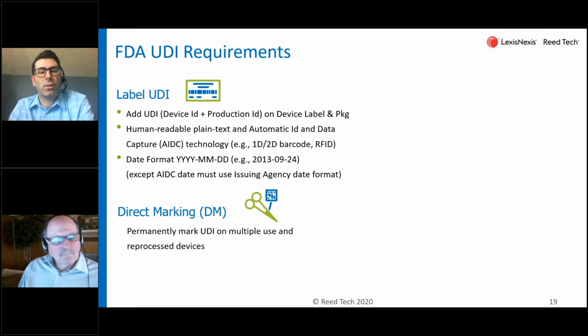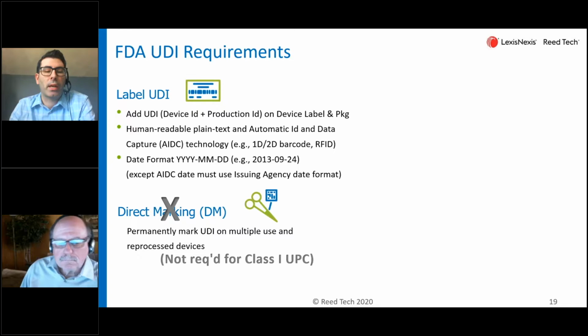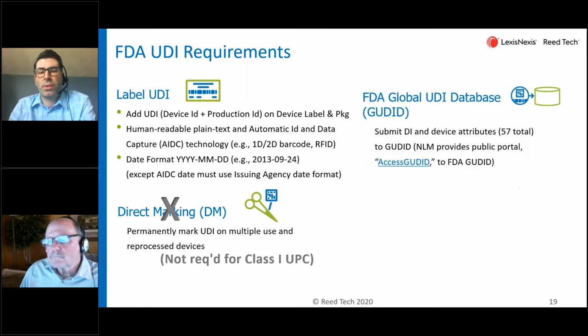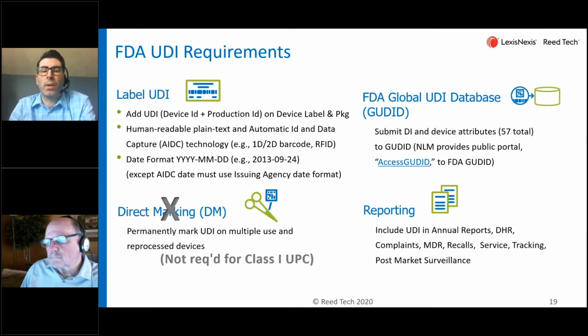You also want to make sure that you have both human readable and machine readable formats on your label. The date format must be labeled as year, month, day. And direct marking does not apply in this particular case if you are utilizing UPCs. Then, of course, the other core component to the UDI requirements is the GUDID. In this case, you would need to submit a total of 57 data attributes. As I mentioned, some of them are required, some are conditionally required depending on what you have populated, and some are optional. And then there's some reporting in the annual reports, the recalls, post-market surveillance, and that sort of thing. Next slide, Gary.